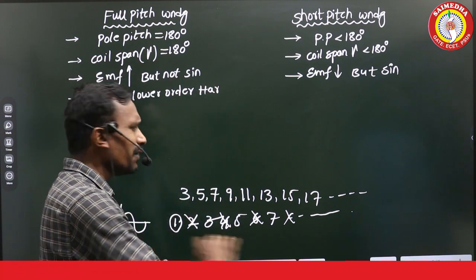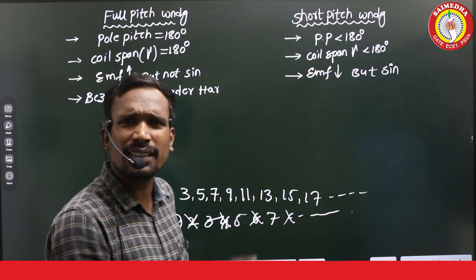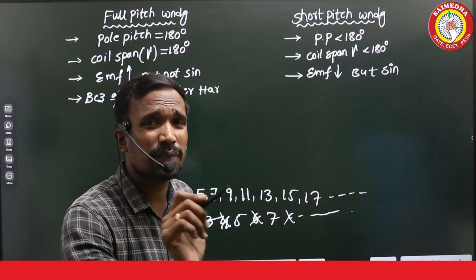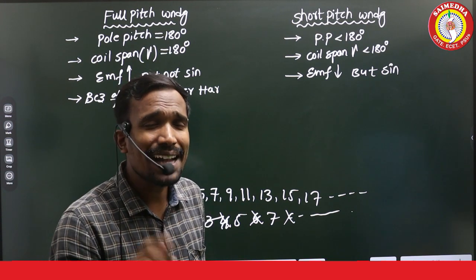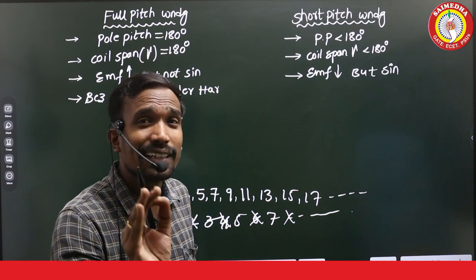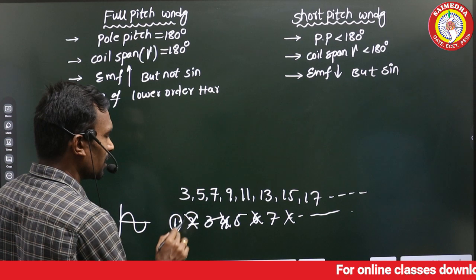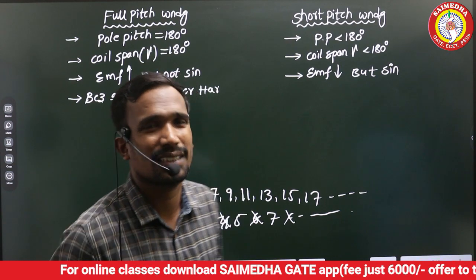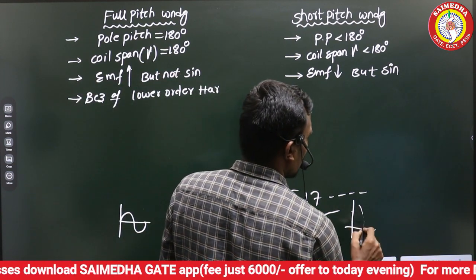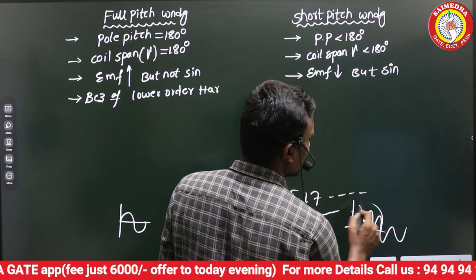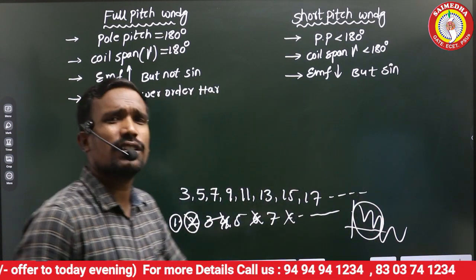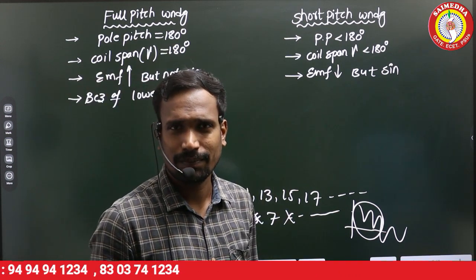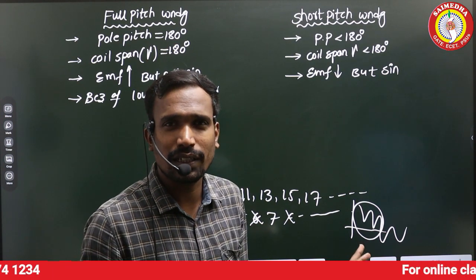Generally, we can't get the concept of even order harmonics except in a transformer. That is somewhat of a deeper concept. What is that? Magnetic inrush currents. In the switching transient concept, the second harmonic is the richest harmonic because the waveform is unsymmetrical to the x-axis. At magnetic inrush currents, the waveform is unsymmetrical to the x-axis in transient state. In transient state, the second harmonic is the richest harmonic. That is only the one concept. Other than that, we can't get a concept for even harmonics.